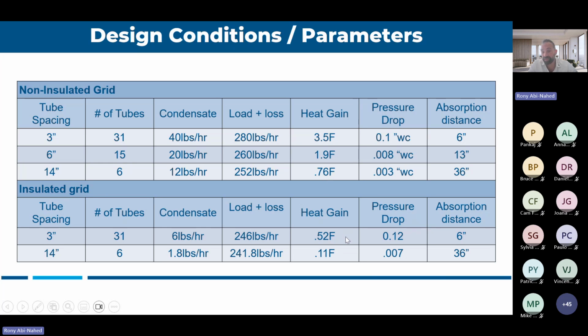Now, the big difference is if you really had 3 feet, but you wanted to go on the safe side and say, I have only 6 inches, because you don't want the headache of condensing. Now that's the issue. For me to give you 6 inches, instead of giving you 6 tubes, I need to give you 31 tubes.